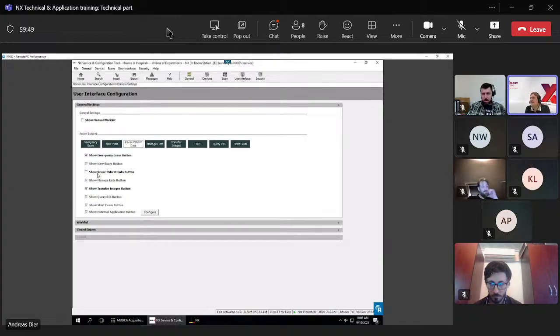The purpose of this is if you have a certain exam and you select this exam, and then you see there are certain thumbnails coming from the RIS, defined by the protocol codes. But it is necessary also to do some other exposures for this patient, which are not in this exam. Maybe there is the rule that if you have additional exposures to be made, then you should do this in an extra exam. You have to make a new one.